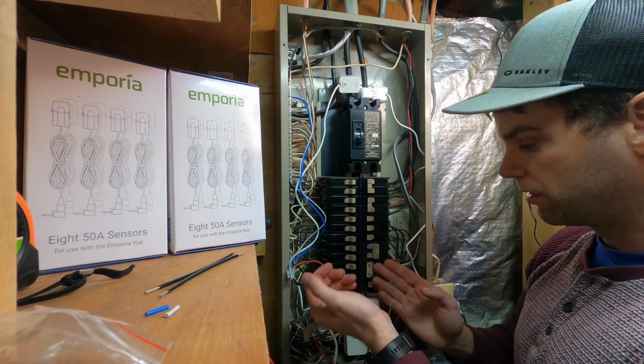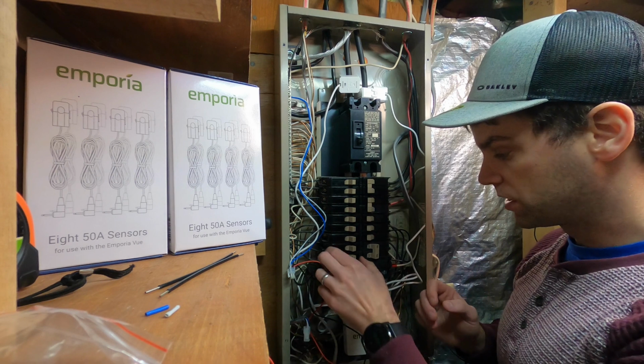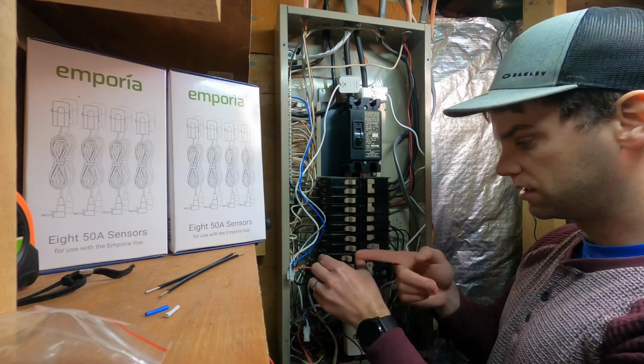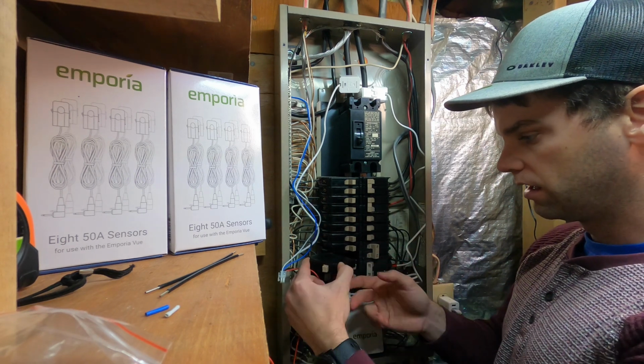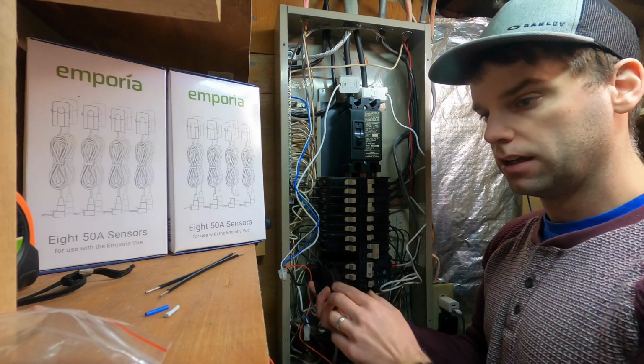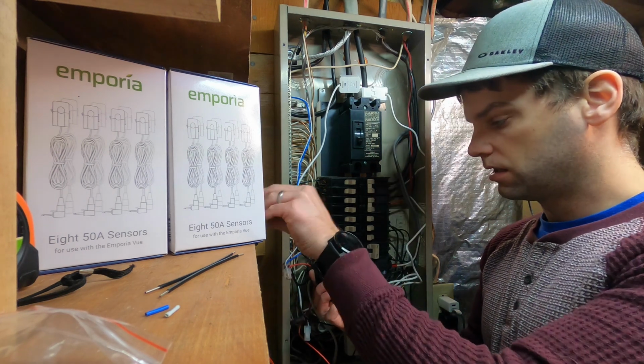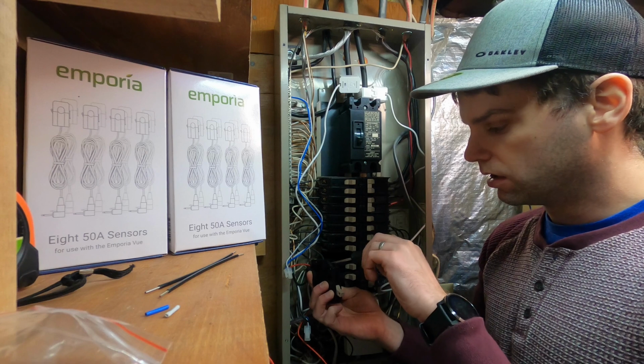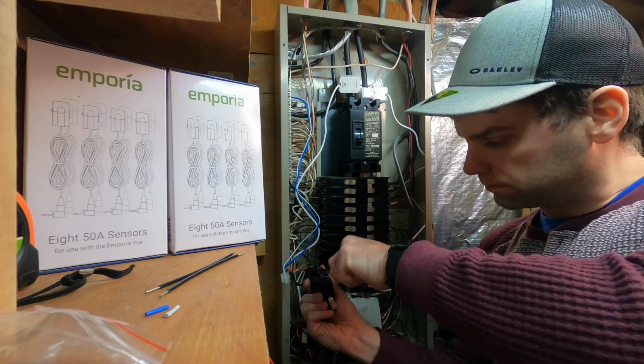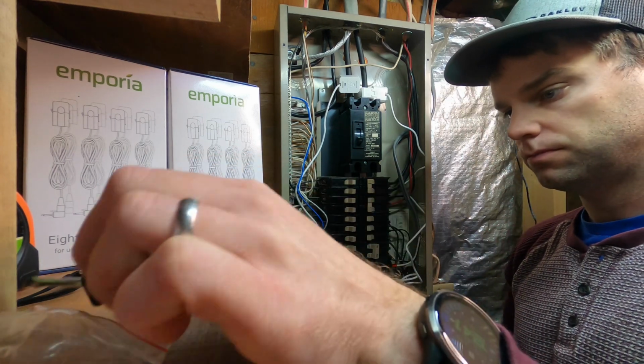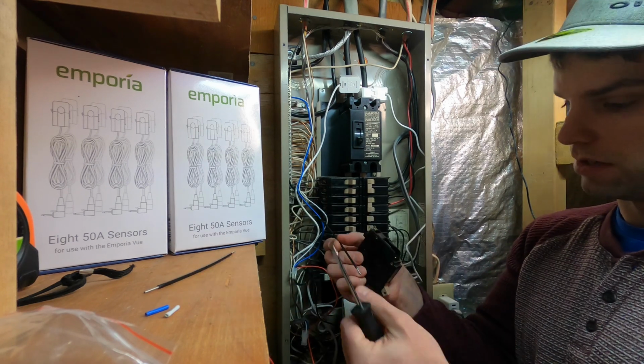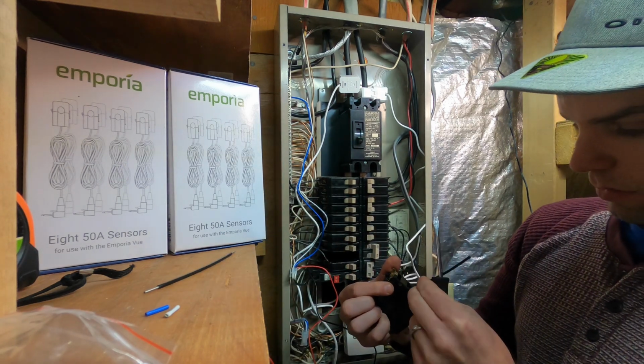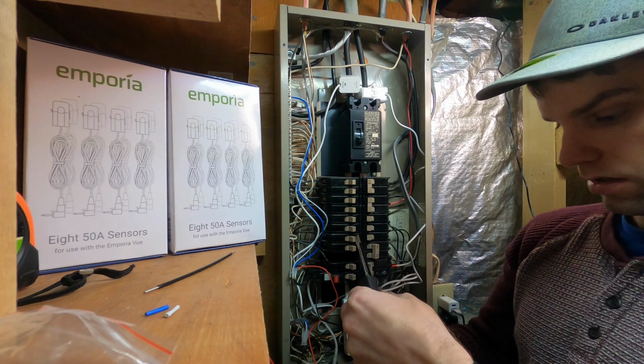So to get these breakers out, it's pretty easy. Most style breakers work like this. You're just going to take and tip it away, and then you're gonna be able to pull this back out. You can see for mine, there's a flathead screw connection here. So I'm just gonna loosen this, and that wire will come out. So what I'm gonna do is take one of my pigtail wires and slip it in here.